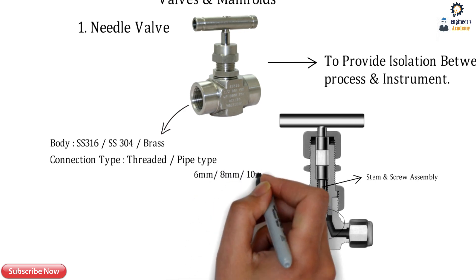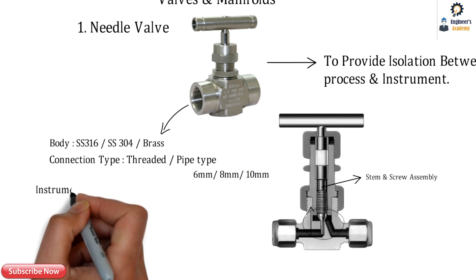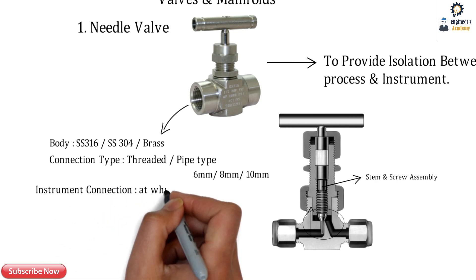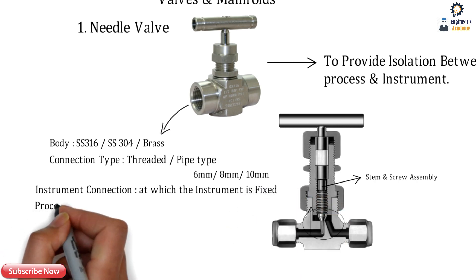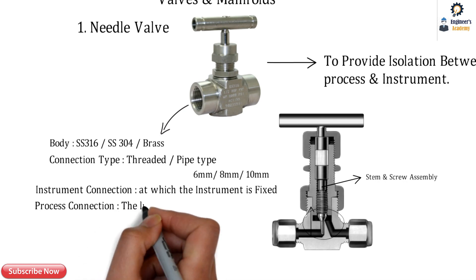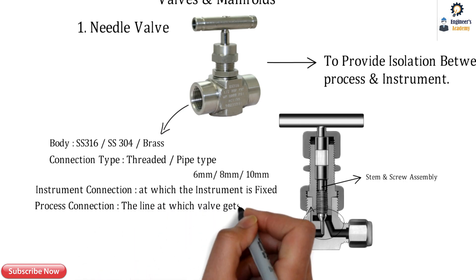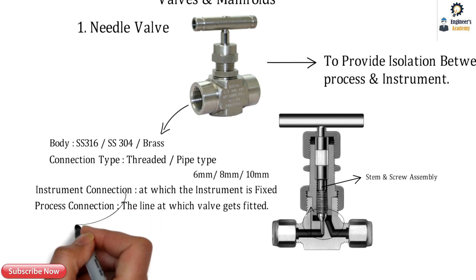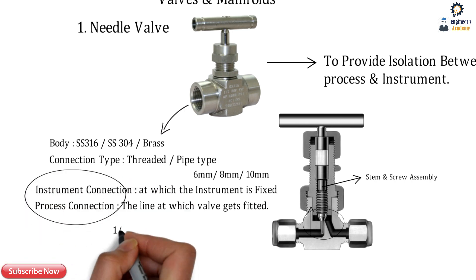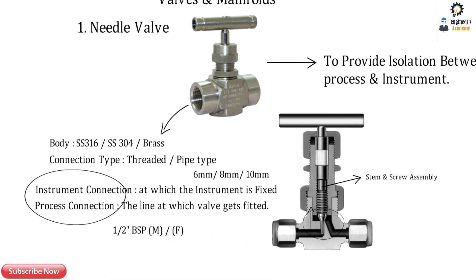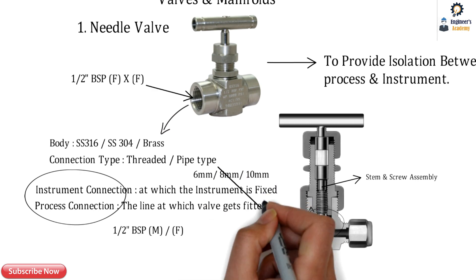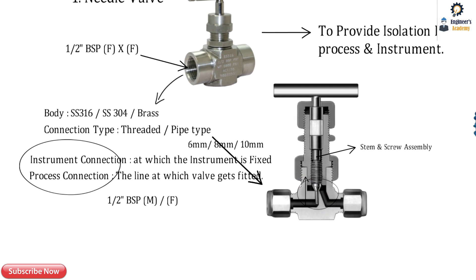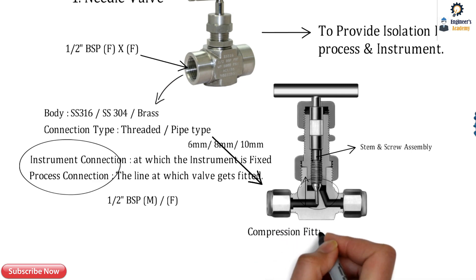The connection type can be threaded process connection or pipe type — 6 mm, 8 mm, or 10 mm pipe — which is essentially a compression fitting. The instrument connection is the side where the instrument gets fixed on the needle valve, and the process connection is the side mounted on the process. These connections can be half inch BSP, NPT, or other thread types. The sectional view also shows the compression fitting type, also known as a compression fitting needle valve.